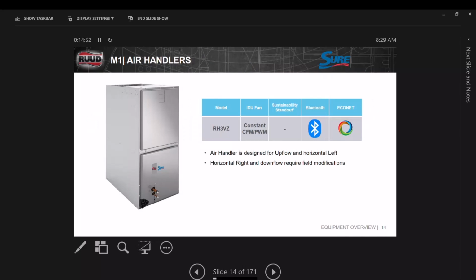The air handlers, the new M1 air handlers, is the RH3VZ model, and it is Bluetooth and EcoNet. All of our air handlers are designed to go upflow or horizontal left, and then you have some modifications you have to do to go right. You probably have already done that before. It's fairly easy. It's not that hard. You can turn the coil around and go right-hand position if you like. Now this unit has a constant CFM PWM type motor, so it's variable speed.